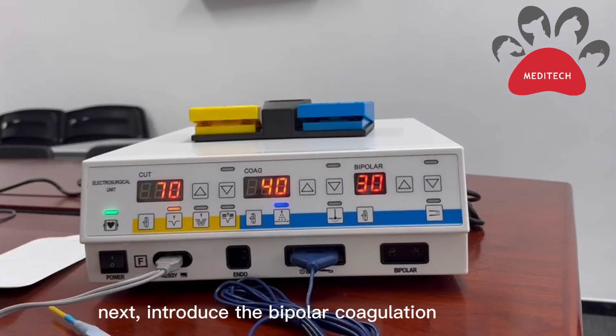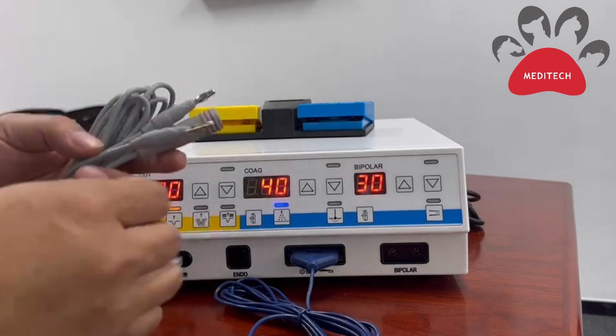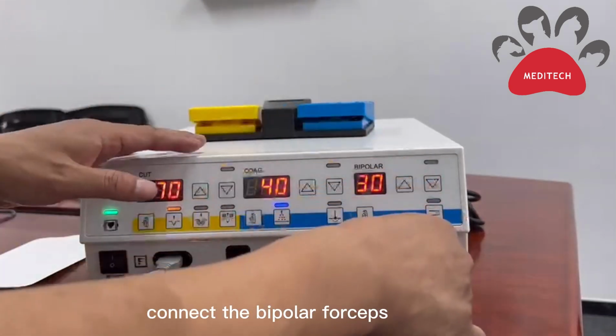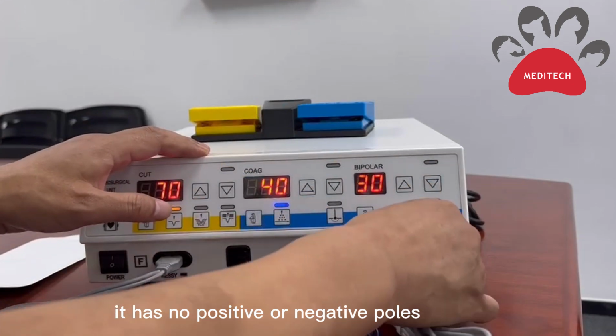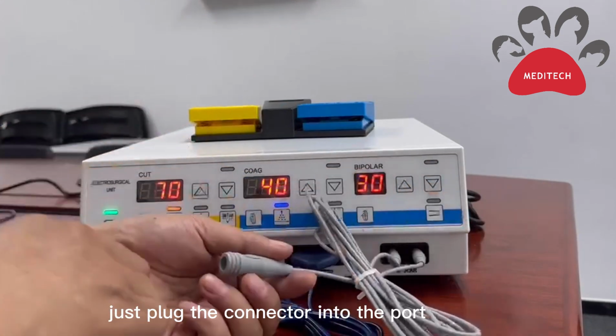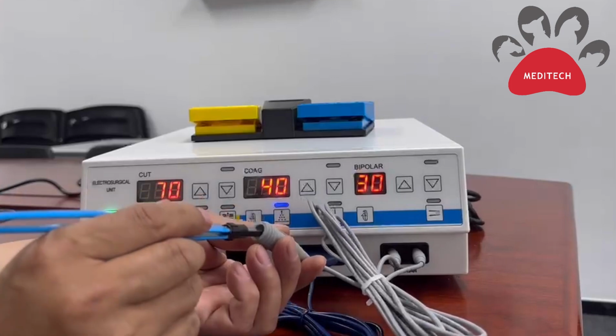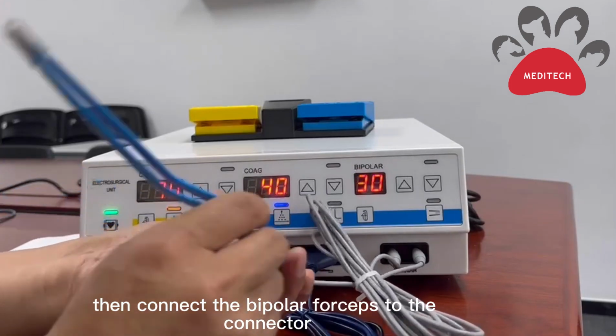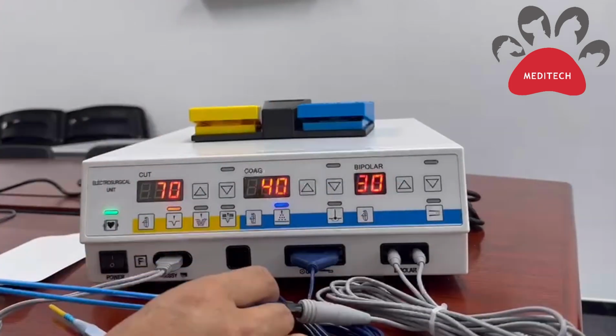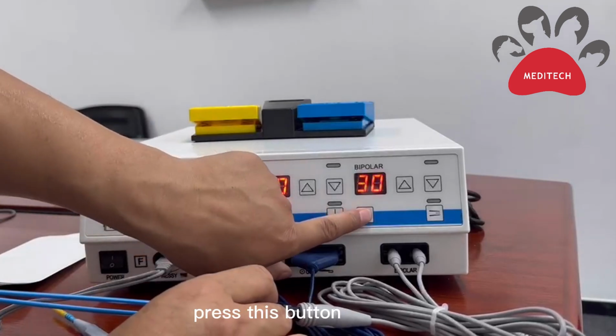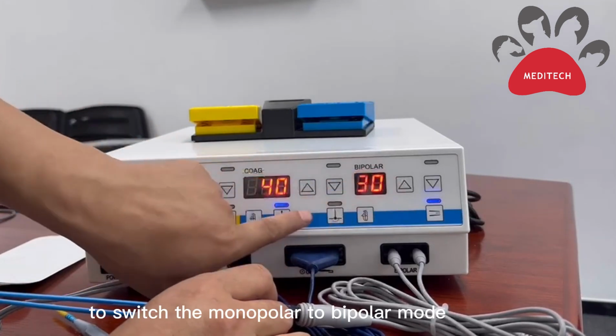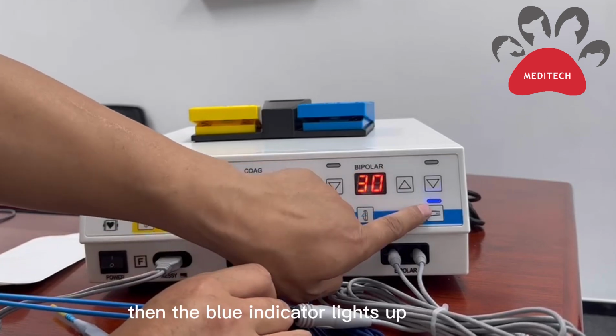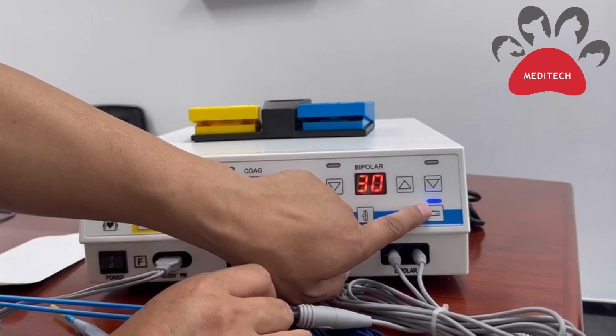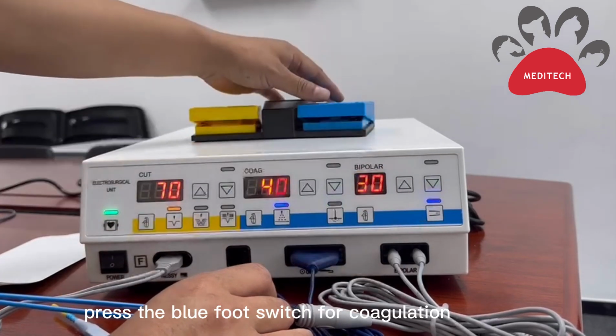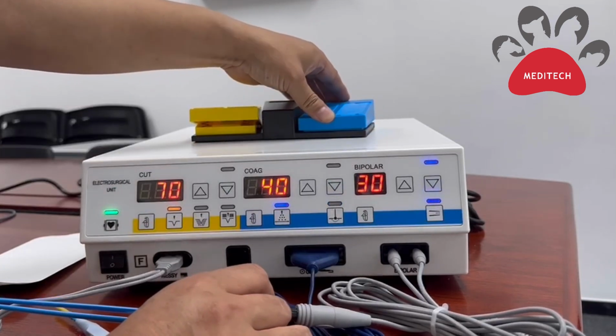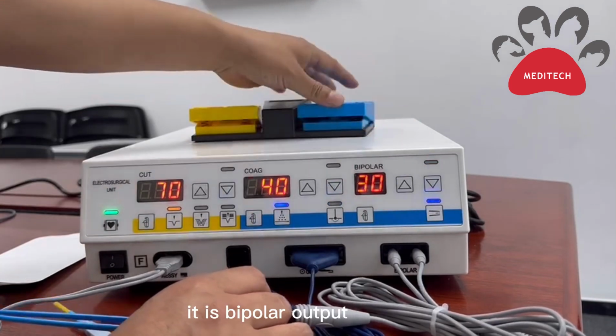Next, we introduce the bipolar coagulation. Connect the bipolar forceps. It has no positive or negative poles. Just plug the connector into the port. Then connect the bipolar forceps to the connector. Press this button to switch from monopolar to bipolar mode. Then the blue indicator lights up. Press the blue foot switch for coagulation. It is bipolar output.